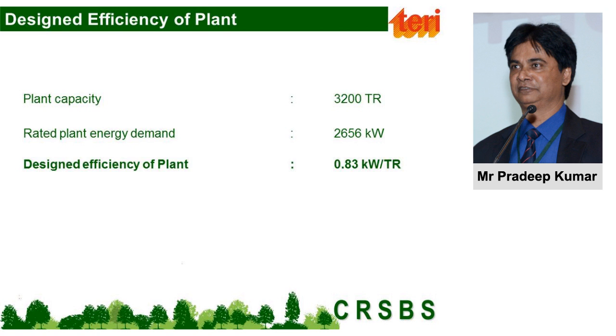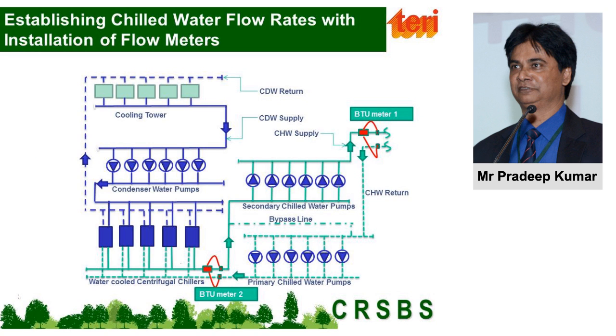Then we noticed, and I think this is happening in all the plants, we don't have proper instrumentation to measure the chilled water or the condenser water. So we requested the client to install 3 flow meters, or BTU meters, meaning 1 flow meter with 2 thermometers, so it can also measure the in and out, supply and return temperatures. For the primary chilled water line, secondary chilled water line, and the condenser water. Later on, the client said that because the condenser water flow is constant speed, first measure the condenser water pumps, and then the same you can install on the secondary one. So we said, fine, we'll do that.